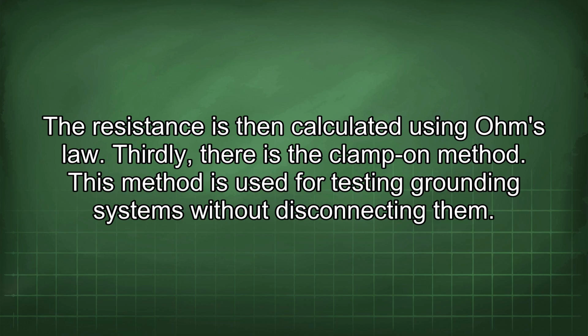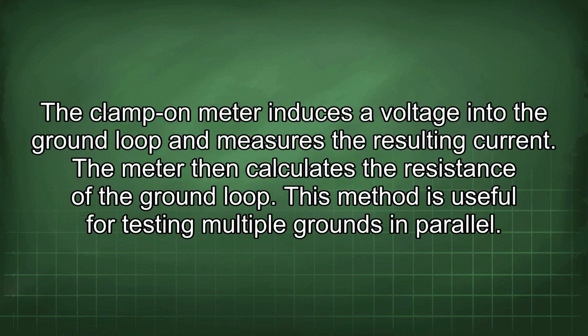Thirdly, there is the clamp-on method. This method is used for testing grounding systems without disconnecting them. The clamp-on meter induces a voltage into the ground loop and measures the resulting current. The meter then calculates the resistance of the ground loop. This method is useful for testing multiple grounds in parallel.